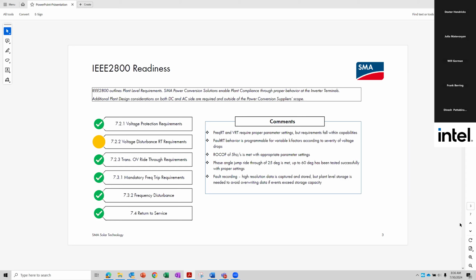And fault recording as a feature has been in SMA equipment for a long time. This is high resolution data. It's almost like having a scope inside the inverter. It captures switching frequency information, DC side information, AC side information, voltage, current, frequency, commands that are going into the inverter. If there are trip signals coming from hardware, software, all of that gets captured pre-fault, during the fault, and post-fault. So we've had this fault recording feature in our inverters for almost 3 generations of inverters.